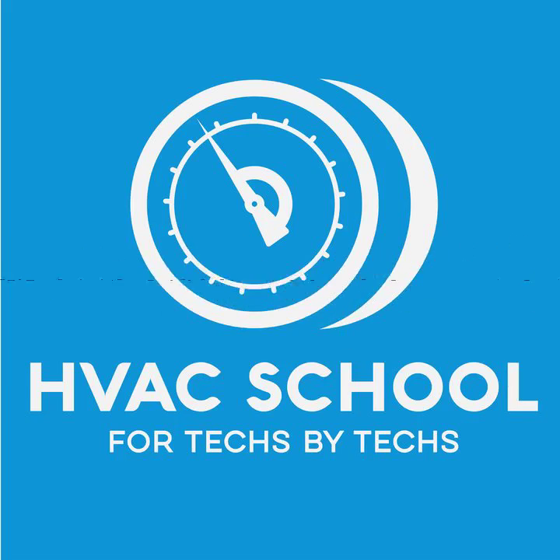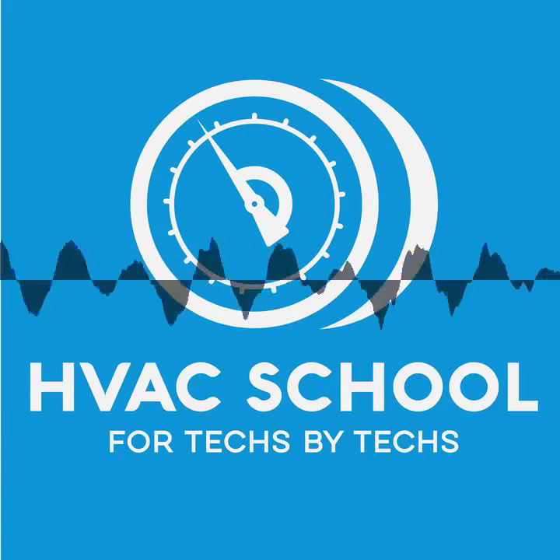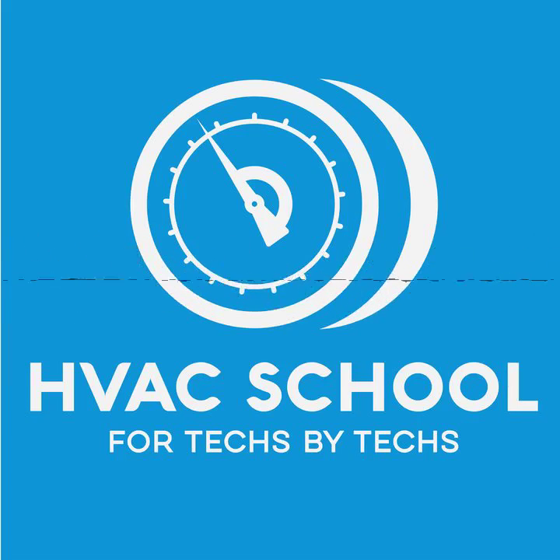Number 8 is power in and power out. I'm interested in this one. Yeah, so to demystify the troubleshooting aspects, if you believe that there is a component failure, first you want to make sure that you have the proper voltage going into the unit on the terminal strip, okay? Then you want to make sure from the terminal strip to the board or boards are getting the proper voltage. If the board isn't lighting up, you're going to check the fuses, because there are going to be some glass fuses on there, most likely, little small fuses.